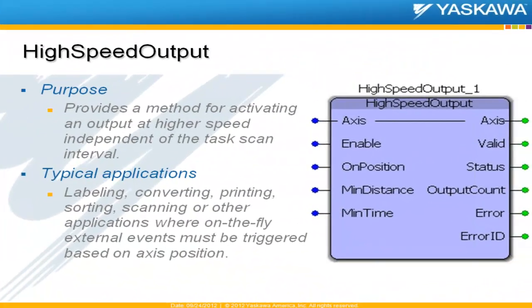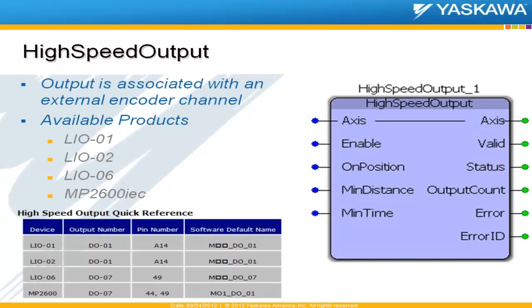The last feature to cover is the high-speed output. We've used this in a couple of high-speed applications. It provides a method for activating an output at high speed, independent of the task scan interval. Applications that might need this include converting or labeling, printing, triggering a vision camera for inspection, or any situation where on-the-fly external events have to be triggered based on axis position.